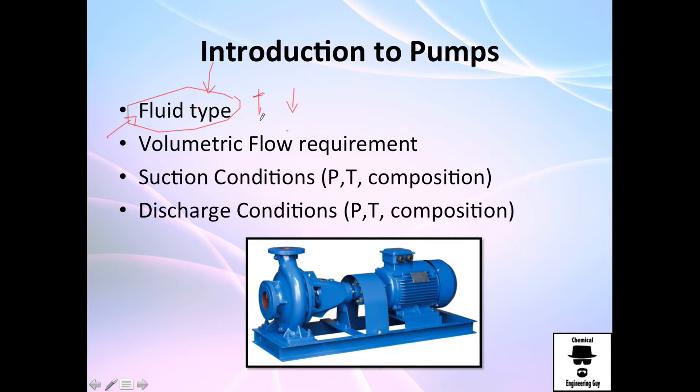Also, of course you need volumetric flow rate. If you have very huge volumetric flow rates, you will be probably using a centrifugal pump. You have very low volumetric flow rates, you are going to use maybe positive displacement pumps.